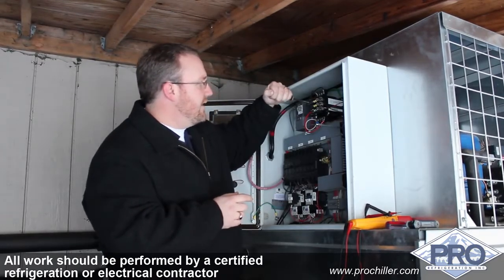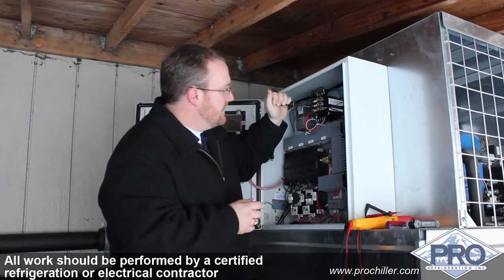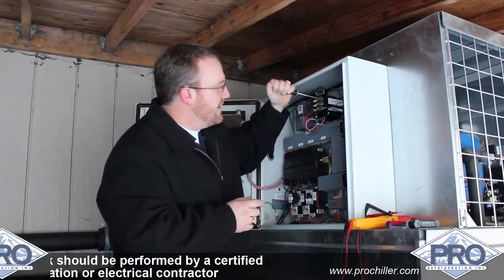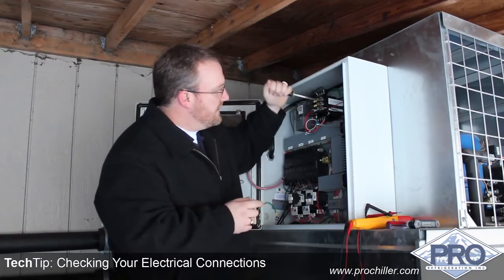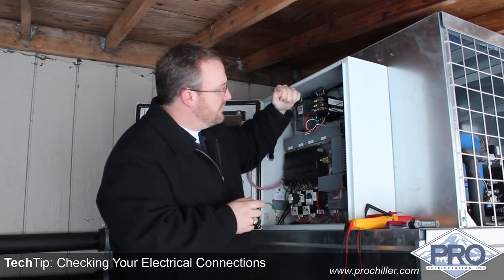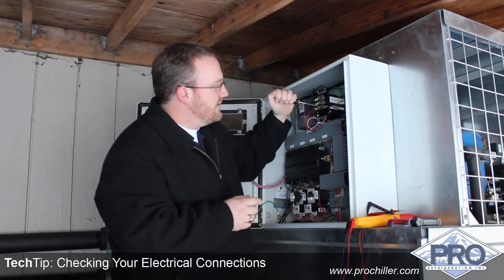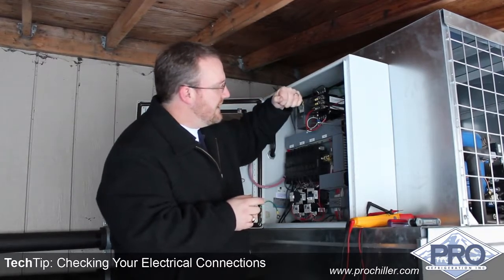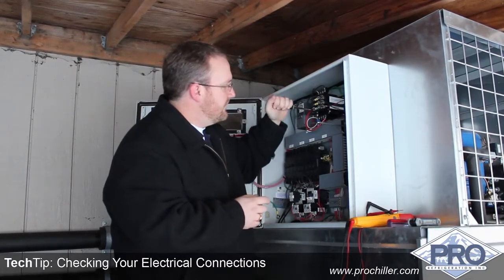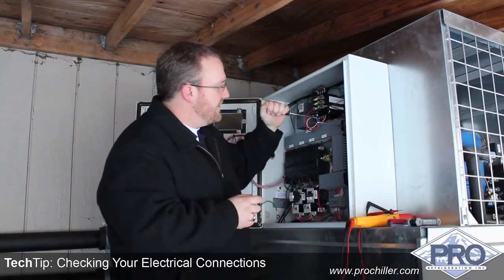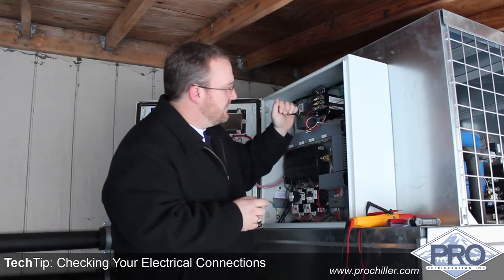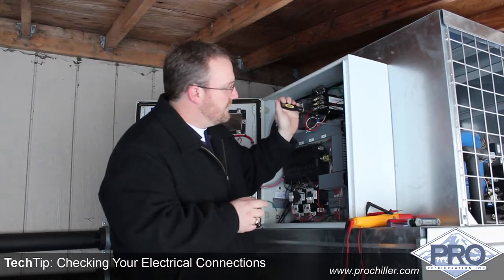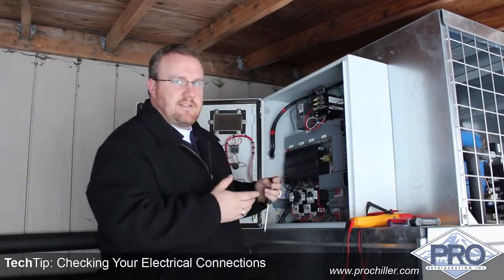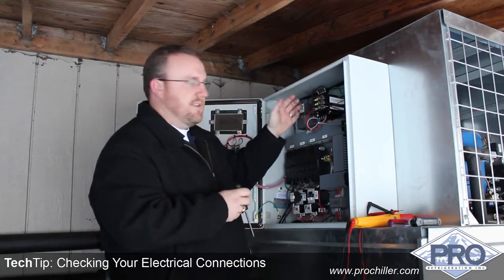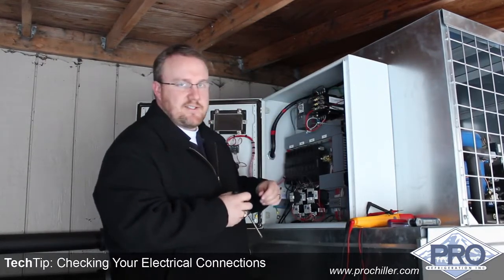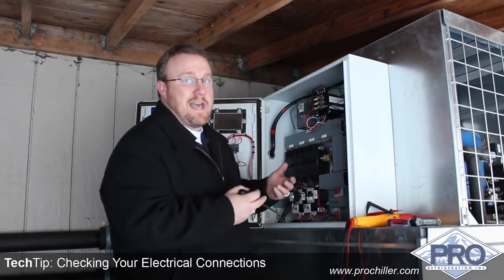So we got about a quarter of a turn out of that one, about a quarter of a turn there, same here. That was about a half a turn, half a turn. That was almost a half a turn. So you can see just off of the control transformer that 6 out of 10 of the screws got a quarter of a turn to a half a turn.